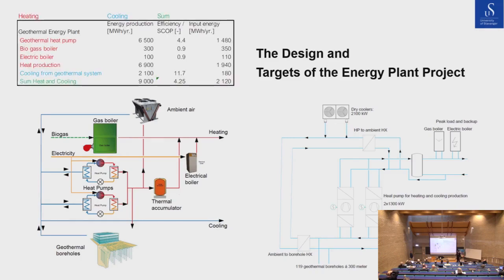The target is to produce about 9,000 megawatt hours of heating and cooling demand with a system COP, coefficient of performance, of about 4.3, giving an input energy, electricity and biogas combined, of about 2,000 megawatt hours per year. We don't really have good numbers on how much energy is used today in the boilers and the electricity consumption, but we do believe that this system will give a reduction of CO2 emissions from the campus heating and cooling system of about 80%.